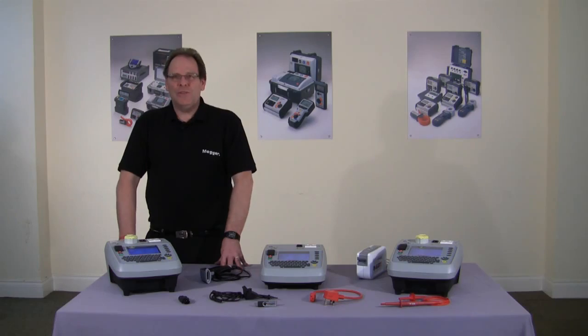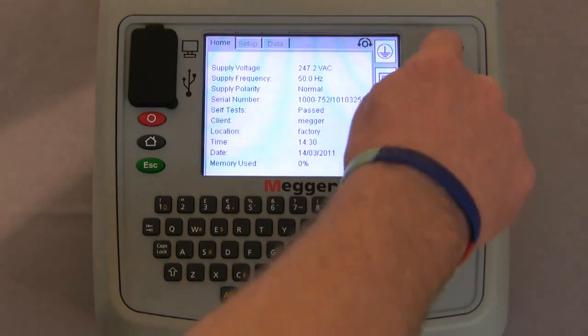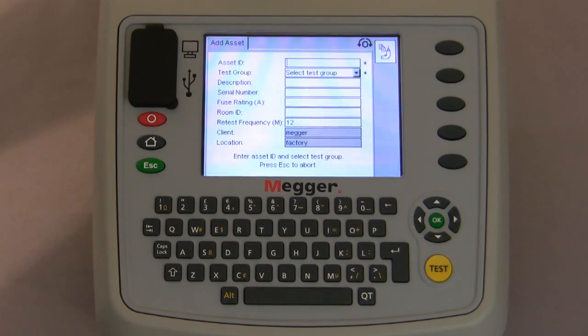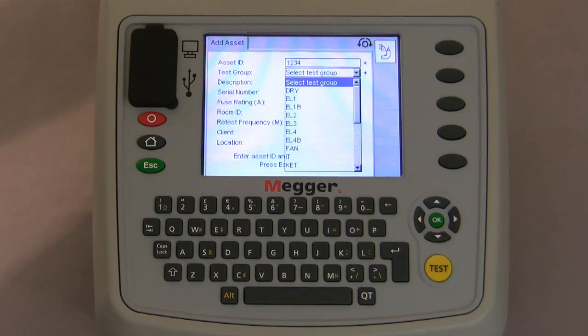Moving on, I'll take you through the procedure of adding an asset. We've added the client which is Megger, the location which is the factory, and now we're going to add an asset. There are two ways to do this. You can select with the hot keys class 1, class 2, extension lead or RCD, carry out the test on the asset and then put the information in afterwards. Alternatively we can press the add asset key, which takes us to the next screen where we can physically add all the information on the asset — the asset identification number. Using the navigation keys we scroll down and select the test group. There are several different codes on screen which are predefined at the factory but you can edit these and add your own.